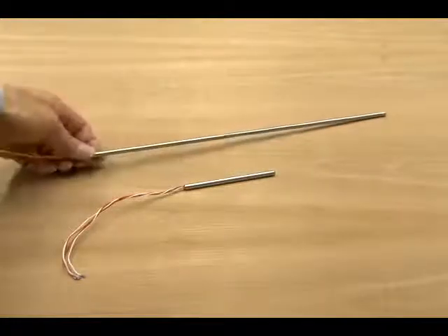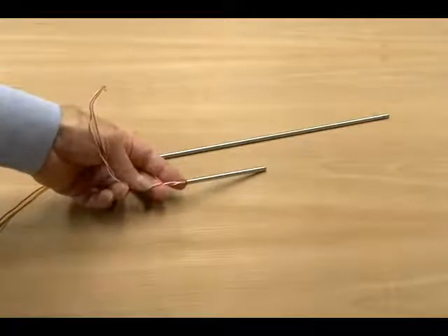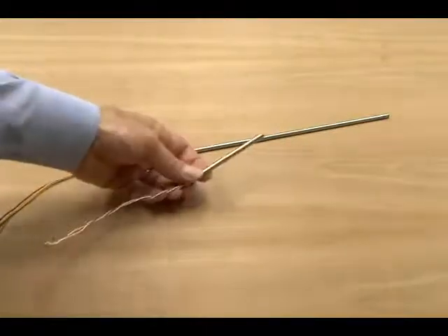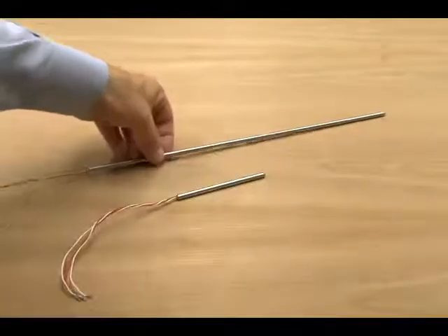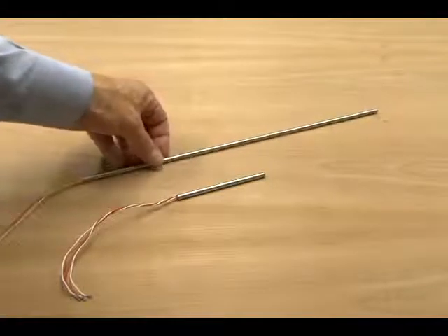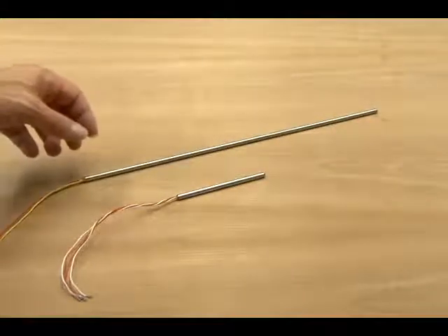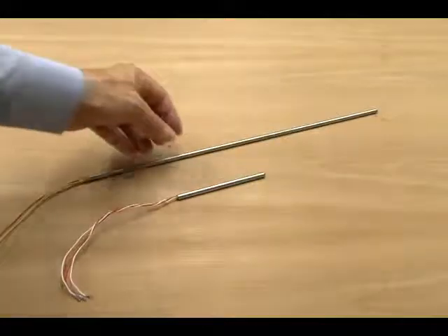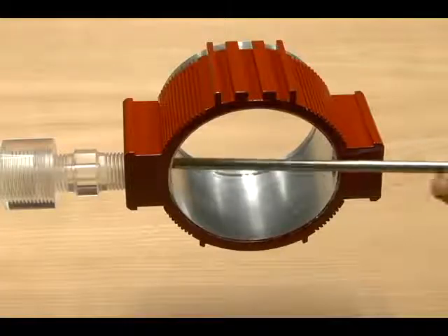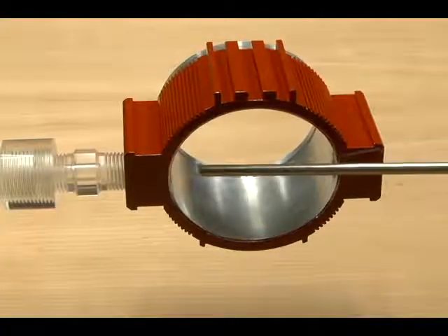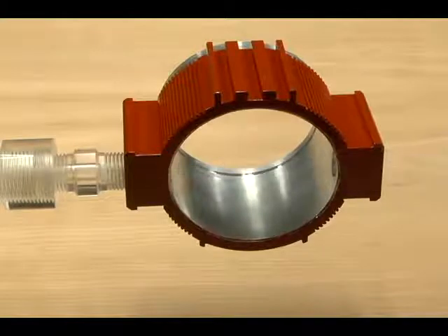It's encased in a rigid stainless steel housing that provides protection without slowing the response time excessively. Where circumstances are favorable, this is an excellent way to go. On the other hand, that rigidity is one of the biggest drawbacks. You must be able to push it straight into the thermal well, which means that you must have its length and more of free space.